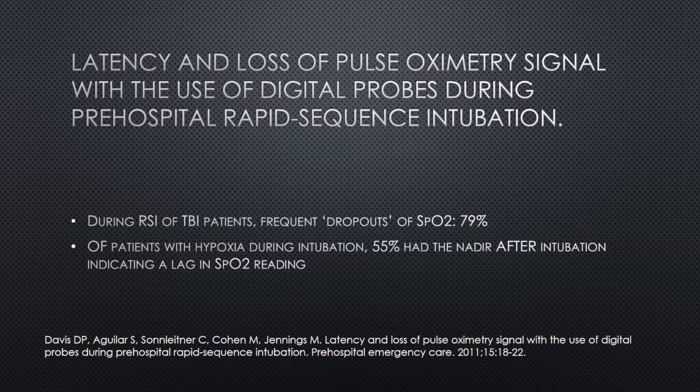Let's talk latency because this is a really big issue, as are dropouts. In looking at some additional intubation of TBI patients, we noticed that dropouts, meaning you have a loss of signal data, so you just have no pulse ox data, occurred in 79% of the patients. And that is a similar number. I think we might have been a little higher in the number of times we lost pulse oximetry data.